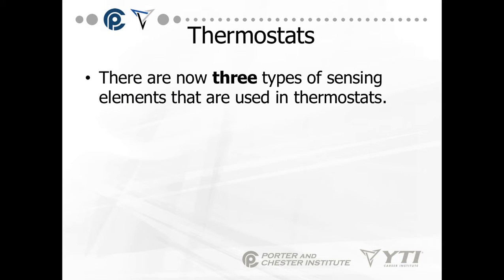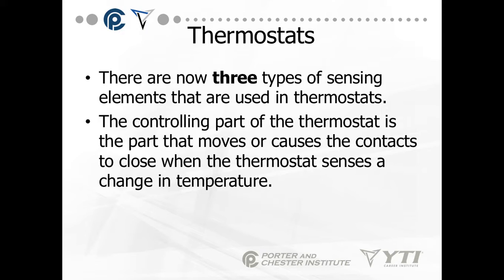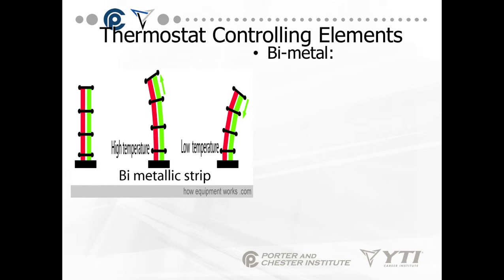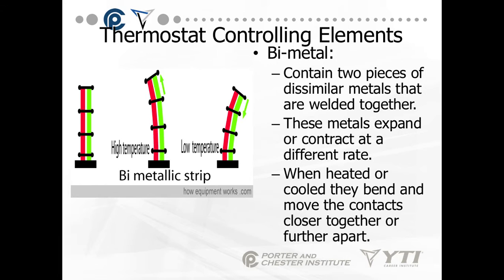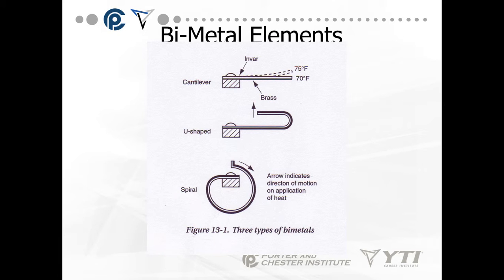There are three types of sensing elements used in thermostats. The controlling part moves or causes the contacts to close when the thermostat senses a change in temperature. The first is the bimetal — a bimetal strip is two dissimilar metals welded together. The different metals expand and contract at different rates, so the whole thing shifts position based on temperature. The bimetal elements you'll most likely see are: cantilever (like a diving board that goes up or down), U-shaped (expands and contracts), and spiral (moves the entire spiral making it bigger or smaller).